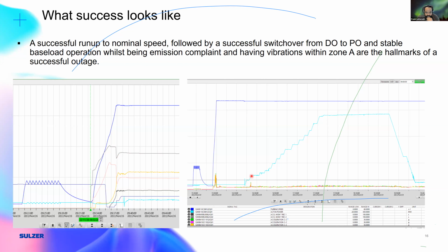And then you would go up in steps until your switchover point, where depending on the type of turbine, whether it's a 94.2 or 94.3, your ball valves activate or you close the diffusion, you open the premix, and then you go up in load again until you hit your base load. You do your heat soaking, and then you come back down again and you switch over at this point. So this would be, let's say, from start to finish, 10 hours, where you take the data that you require for your analysis to make sure that the unit is up and running, your vibrations are all okay, and you release the machine for commercial operation.